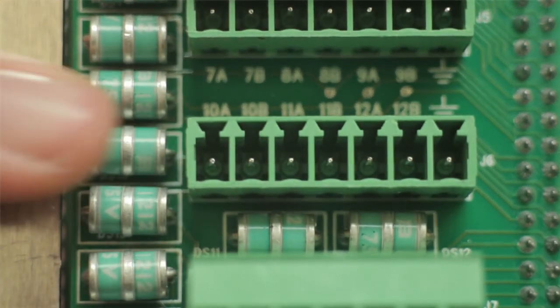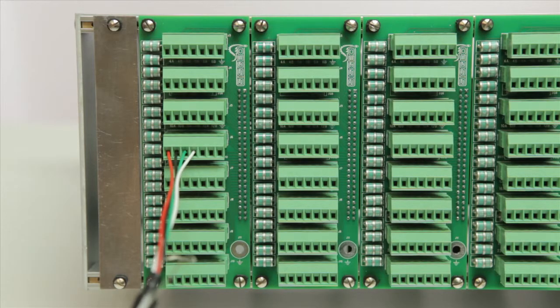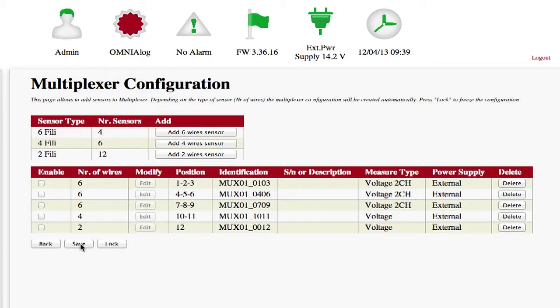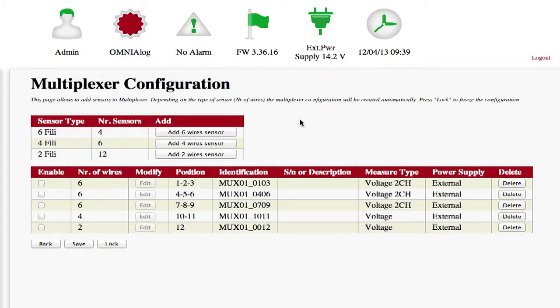It is important to first configure the instruments and then connect them to the multiplexer. As instruments are gradually added, the number of instruments available is automatically stepped down in the NRSensors function. This means the user is always aware of the number of instruments, subdivided by type, which can still be added to the multiplexer. When you have finished adding the sensors, press the Save button to confirm the changes.